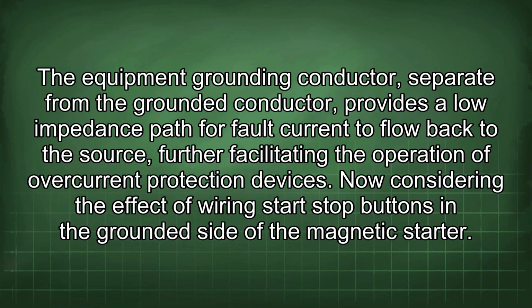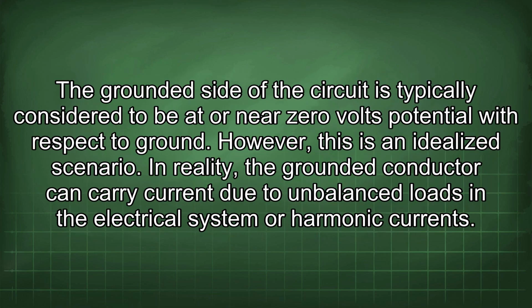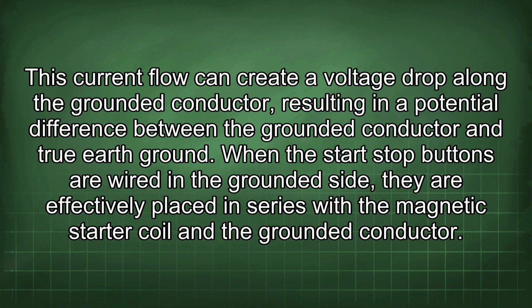Now considering the effect of wiring start-stop buttons in the grounded side of the magnetic starter. The grounded side of the circuit is typically considered to be at or near 0 volts potential with respect to ground. However, this is an idealized scenario. In reality, the grounded conductor can carry current due to unbalanced loads in the electrical system or harmonic currents. This current flow can create a voltage drop along the grounded conductor, resulting in a potential difference between the grounded conductor and true earth ground.